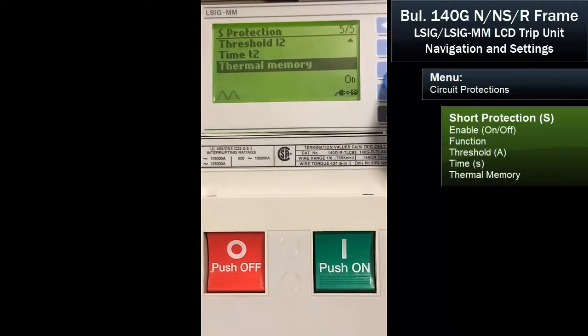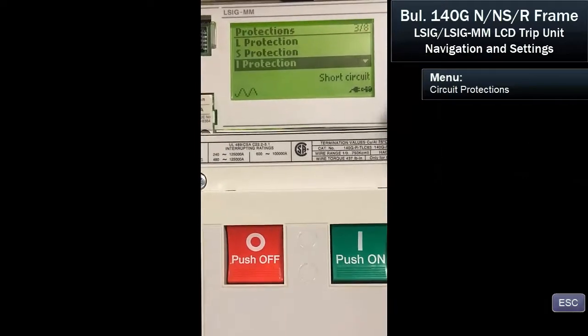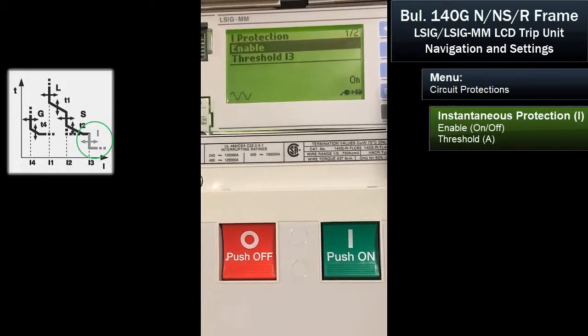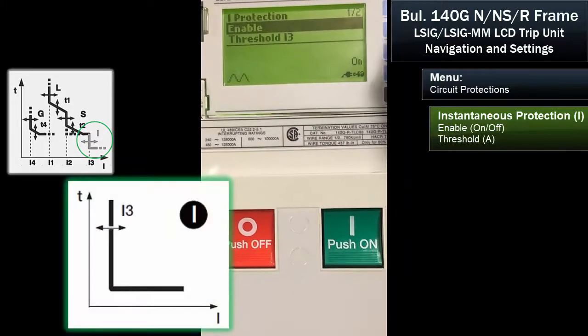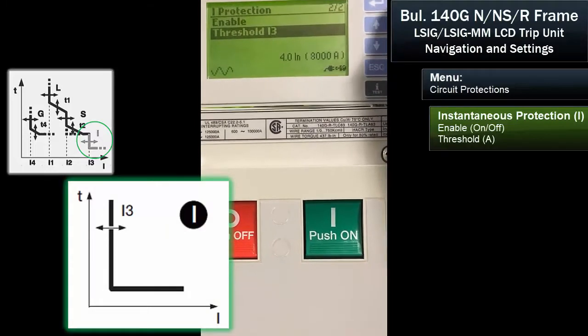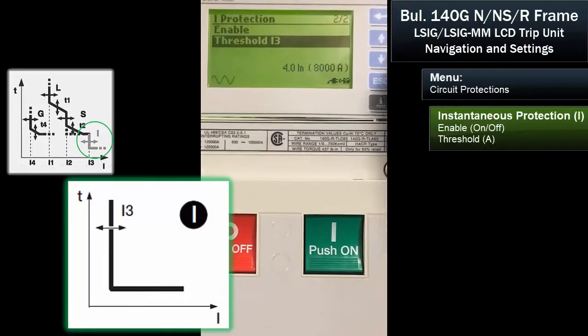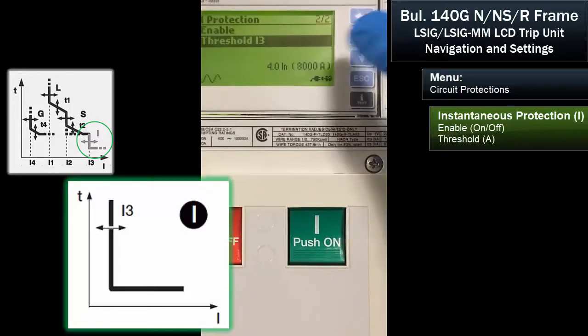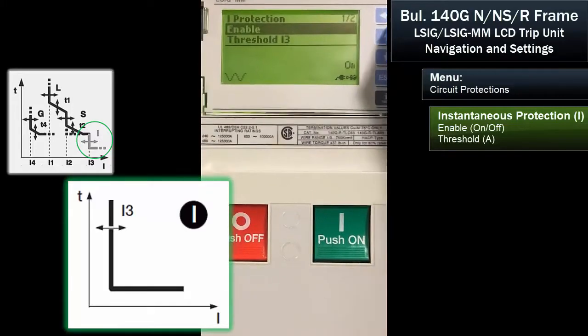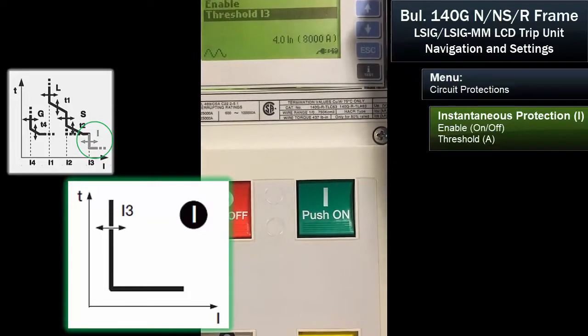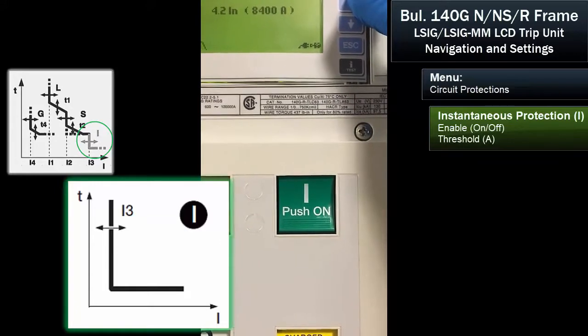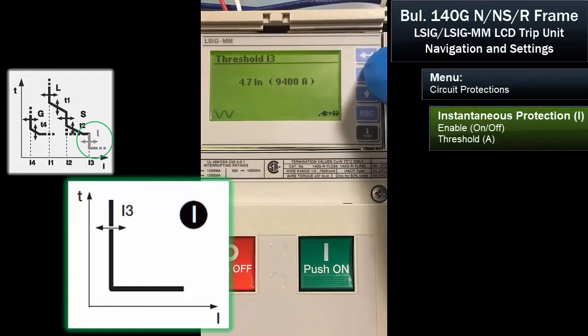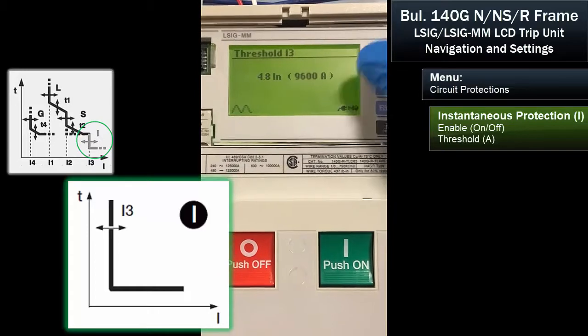We've set thermal memory. Now we want to set our instantaneous protection. We've enabled it. That's I, or instantaneous, also called I3 when we look at the current protections. We're going to look at the threshold — it's currently set at four times. I'll set it a little bit higher so that we don't have nuisance tripping.